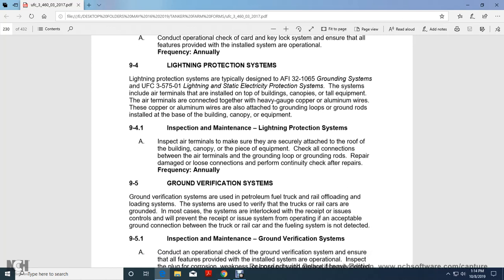Inspection and maintenance of the lightning protection system. Inspect the air terminals to make sure they are securely attached to the roof of the building, canopy, or piece of equipment. Check all of the connections between the air terminals, the ground loop, and the ground rods. Repair any damaged or loose connections. Perform continuity checks after repairs, annually.